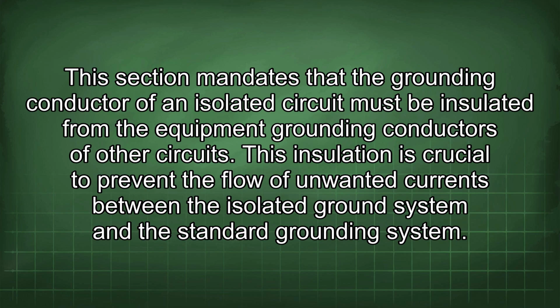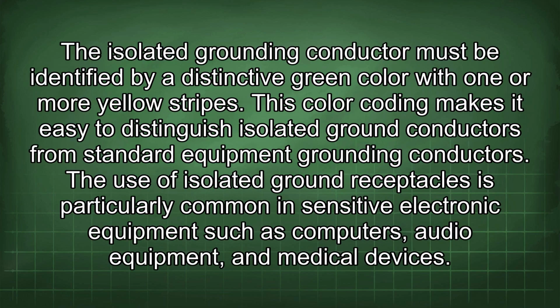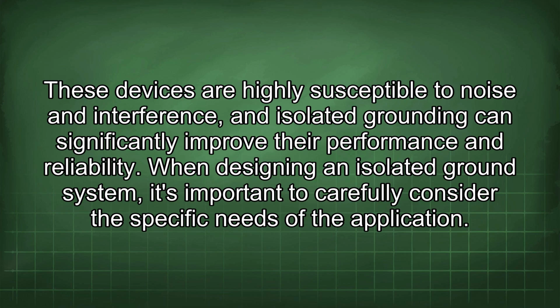standard grounding system. The isolated grounding conductor must be identified by a distinctive green color with one or more yellow stripes. This color coding makes it easy to distinguish isolated ground conductors from standard equipment grounding conductors. The use of isolated ground receptacles is particularly common in sensitive electronic equipment such as computers, audio equipment, and medical devices. These devices are highly susceptible to noise and interference, and isolated grounding can significantly improve their performance and reliability.